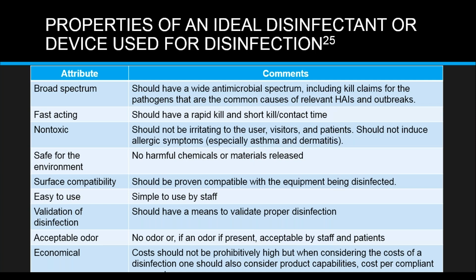One uses ultraviolet light. It's chemical-free. The other is a hydrogen peroxide mist device that uses 35% hydrogen peroxide. But we're going to focus first on ultraviolet light. So this device here delivers ultraviolet C light, which is defined as, in this case, 254 nanometers. It's a specific wavelength. As particles and waves, it's reflected from the chamber walls and ensures there's no shadowing.